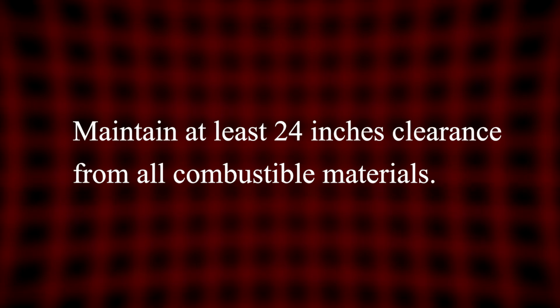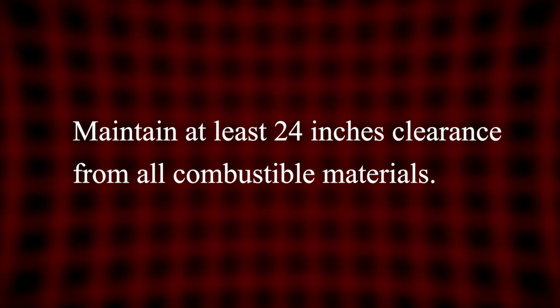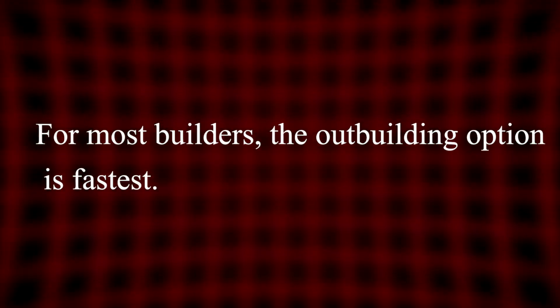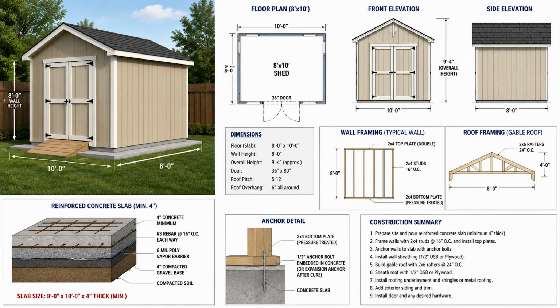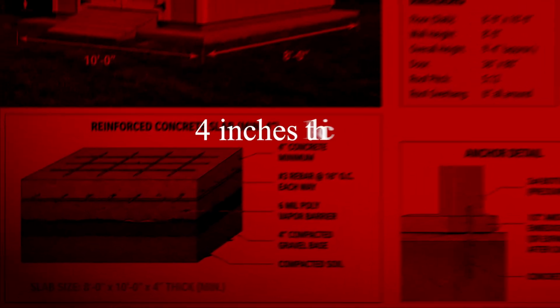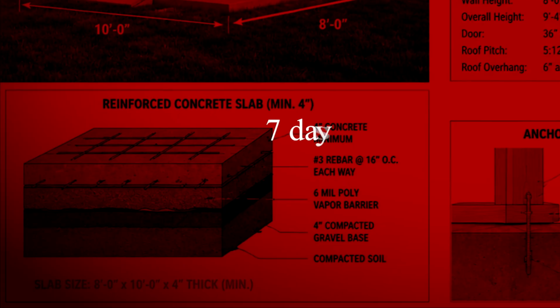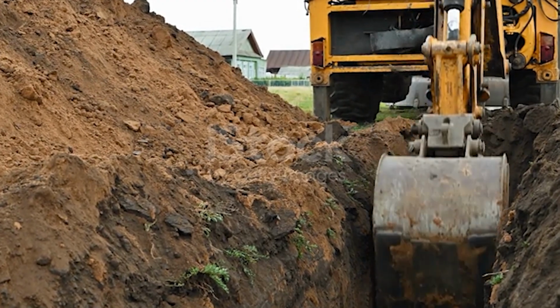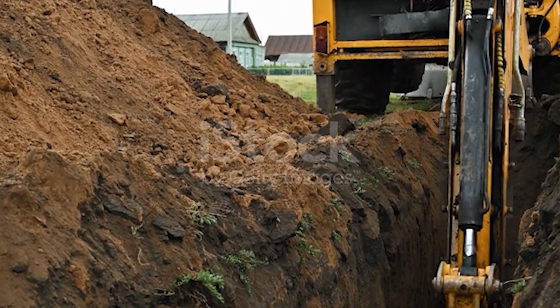Option 3. Place it in an attached utility room with concrete or masonry walls and proper fire separation. Maintain at least 24 inches clearance from all combustible materials. For most builders, the outbuilding option is fastest. Construct a simple 8 by 10 foot shed on a reinforced concrete slab at least 4 inches thick. Allow the slab to cure for 7 days before setting the heavy tank. A filled 250-gallon unit weighs over 1 ton. For underground pipe runs, dig trenches at least 18 inches deep below frost line and use pre-insulated pipe sleeves.